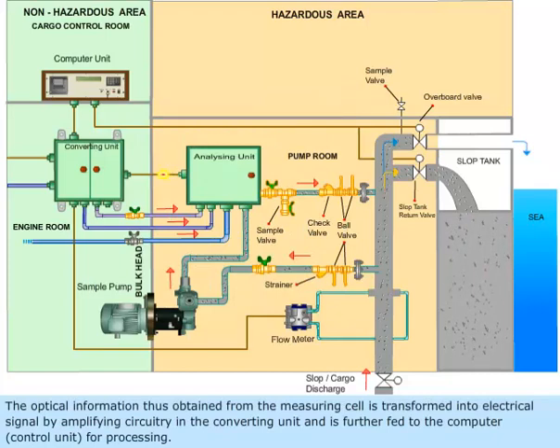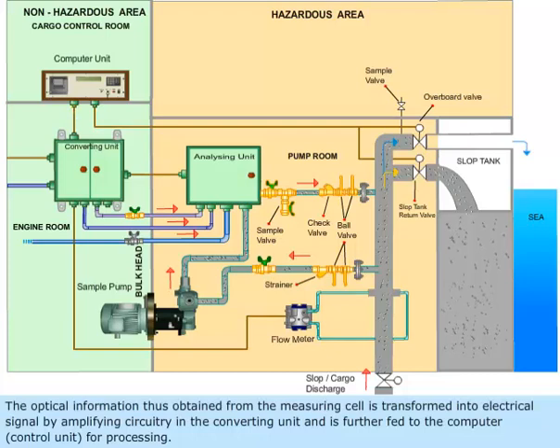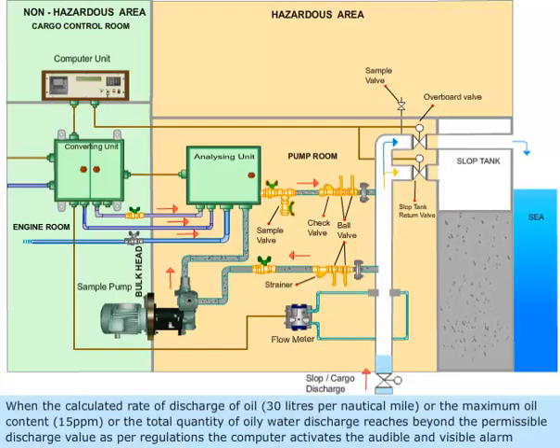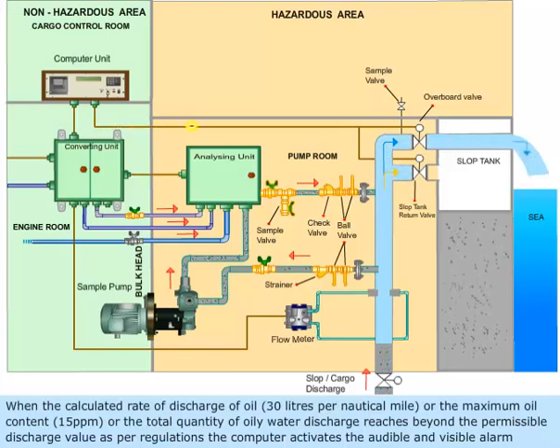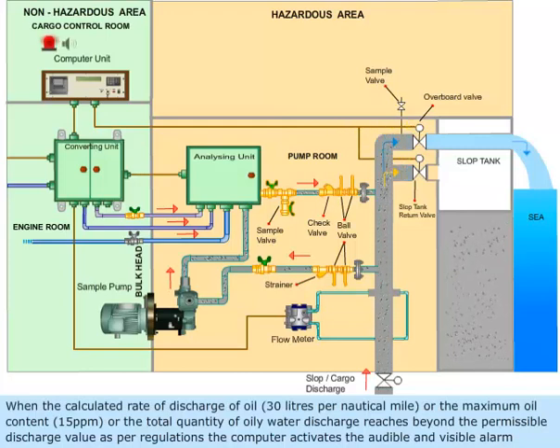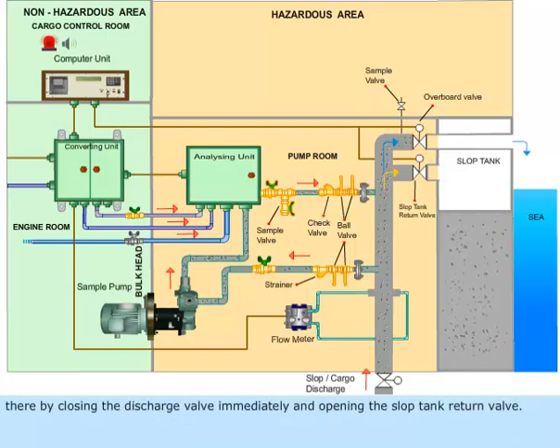The optical information obtained from the measuring cell is transformed into an electrical signal by amplifying circuitry in the converting unit and is further fed to the computer control unit for processing. When the calculated rate of discharge of oil reaches 30 liters per nautical mile, or the maximum oil content reaches 15 ppm, or the total quantity of oily water discharge exceeds the permissible discharge value as per regulations, the computer activates audible and visible alarms, immediately closing the discharge valve and opening the slop tank return valve.